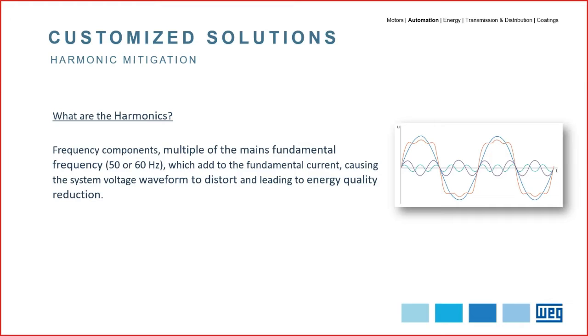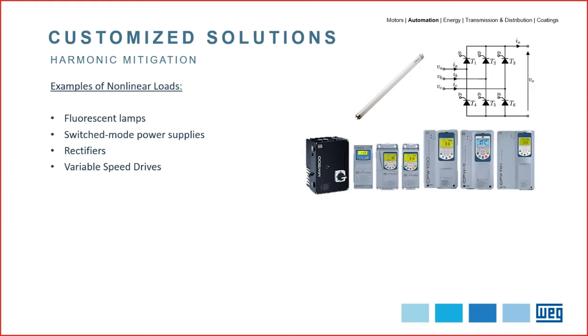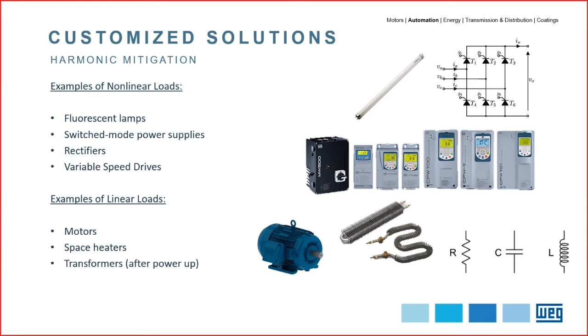So, what are these harmonics? In short words, harmonics are frequency components, multiple of the mains fundamental frequency, which add to the fundamental current, causing the system voltage form to distort and leading to an energy quality reduction. Harmonic currents are produced by nonlinear loads that are in the power system. Now, some examples of nonlinear loads are fluorescent lamps, switch mode power supplies, rectifiers, and frequency inverters. Basically, all semiconductor equipments. And some examples of linear loads are motors, space heaters, transformers after power up, and incandescent light bulbs.